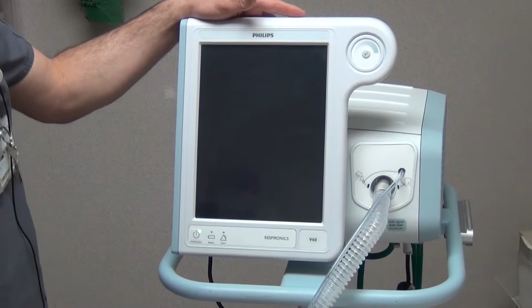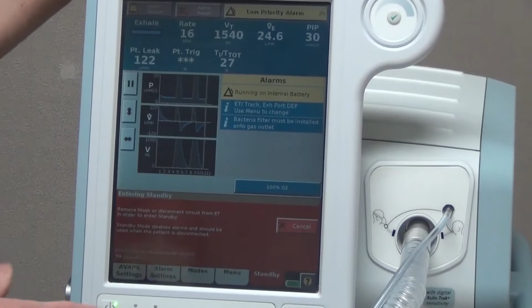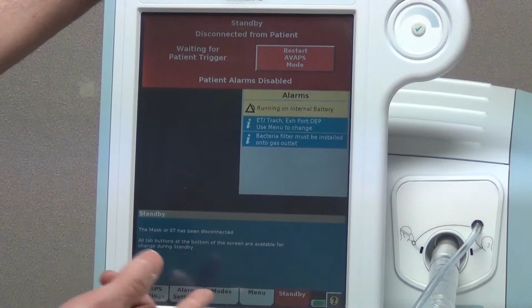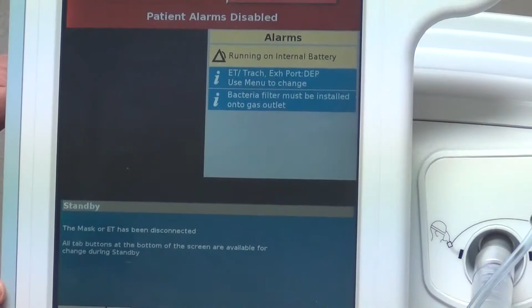To turn on the machine, you're going to push a button. It's going to make some noise and you're going to hear it kick on and blow some air. Once you have that on, can you see the screen okay with the light on? All right. What we're going to do is hit standby. This will stop the machine from ventilating while we're setting the settings into the machine. Notice it says running on internal battery. This machine does have a battery.